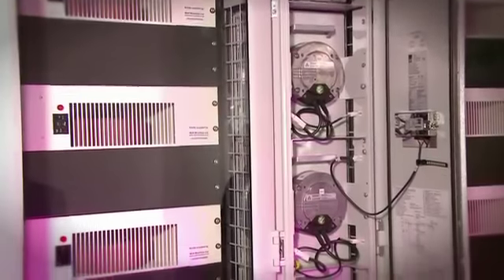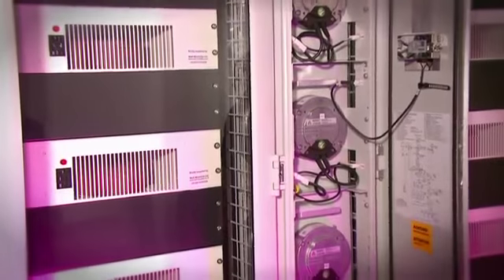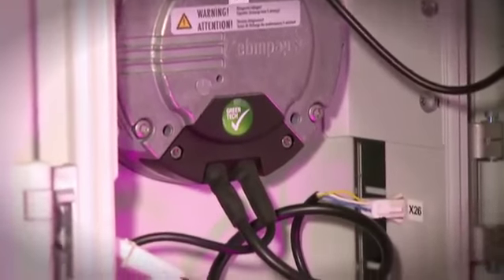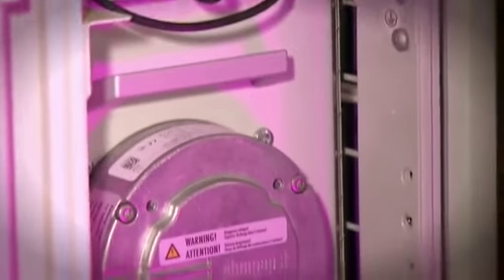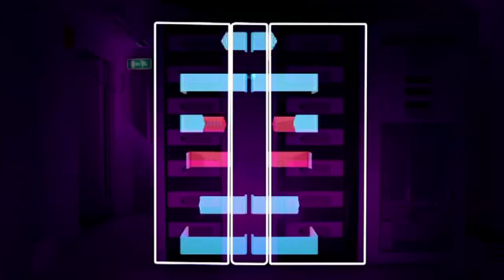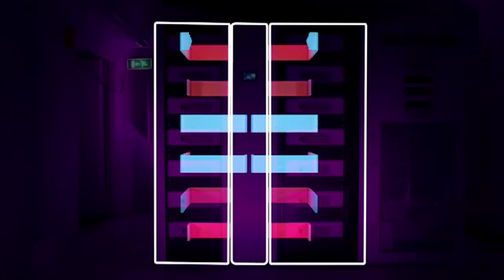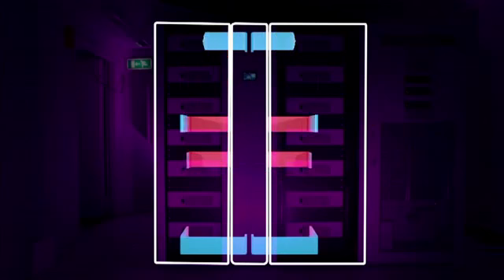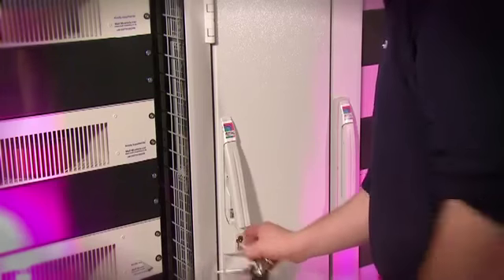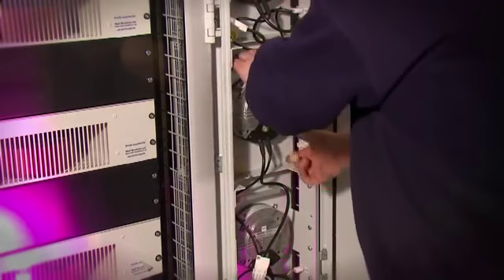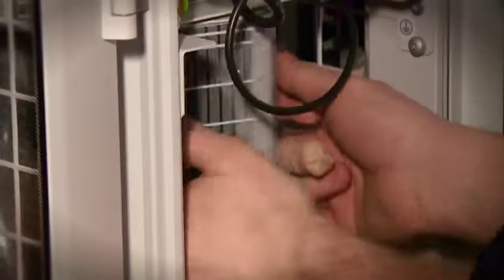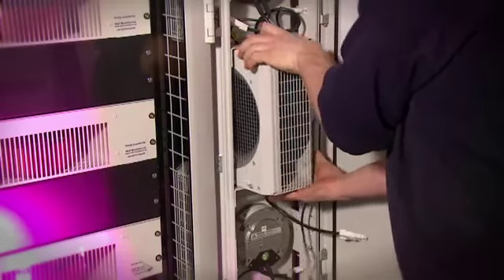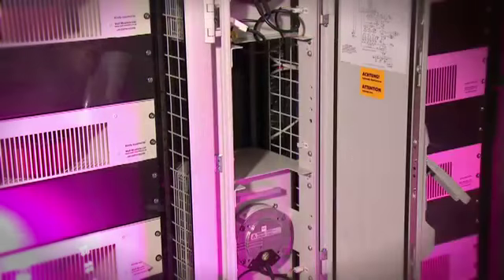The fans that pull the air through the heat exchanger are fed from a single 3-phase supply, 2 fans per phase. Therefore, in the event of a phase failure, 2/3 of your fans are still working. The remaining fans will automatically speed up to compensate for the 2 that have shut down. Each fan module is hot swappable and can be removed and replaced in seconds, minimizing the mean time to repair and maximizing the mean time between failure was one of the key design considerations for LCP Plus.